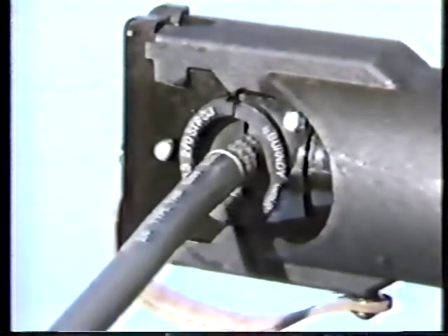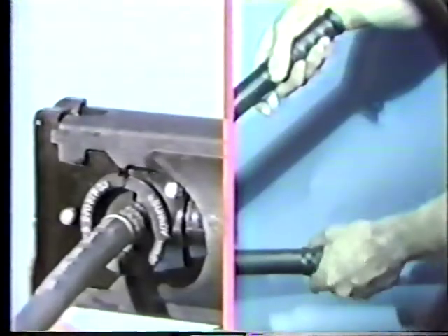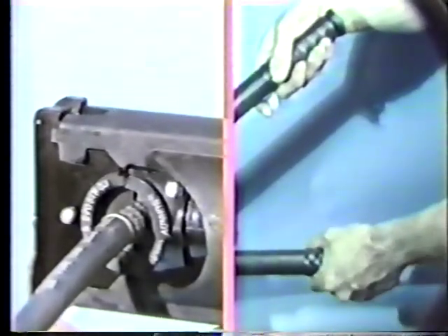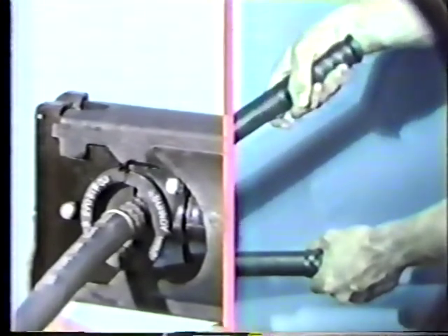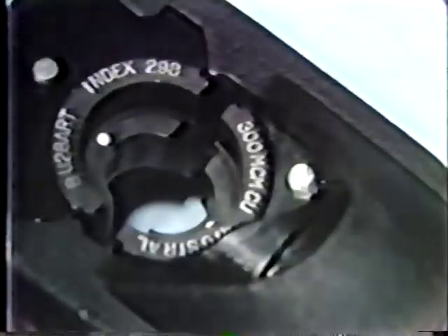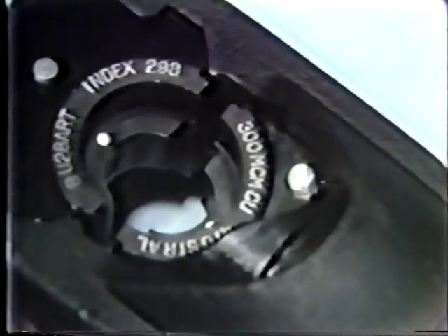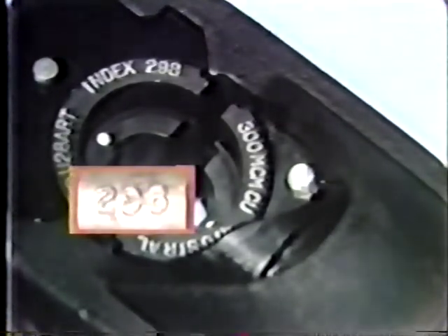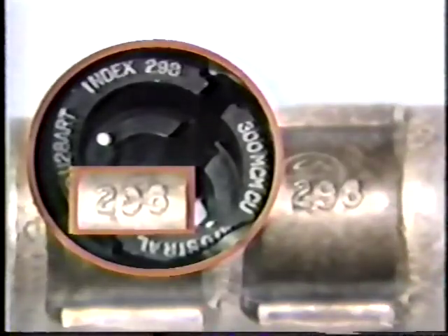When the proper pressure is attained, the tool's pressure release valve will automatically blow off, producing an audible sound and sudden release of handle pressure. To remove the connector, rotate the handle one turn in the counterclockwise direction, then squeeze the trigger while closing the handle. For instant inspection, this installation system will emboss a die index number, which matches the number on the connector. If splices or aluminum connectors are being installed, the crimps are placed between the color-coded rings or knurlings.